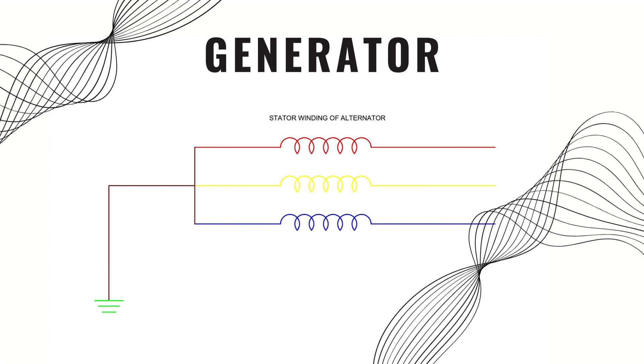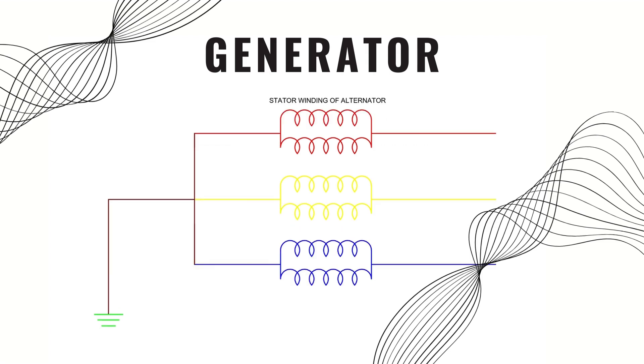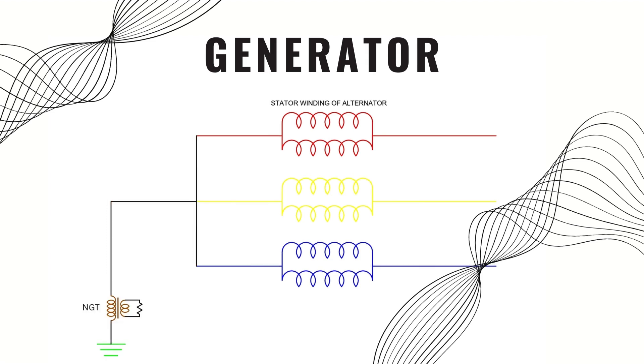Actually, the stator of the generator is connected in a double star connection method. This means that there are two windings connected parallel in each phase and each phase is connected in star configuration. On the neutral side, there is a neutral grounding transformer through which the neutral is grounded.